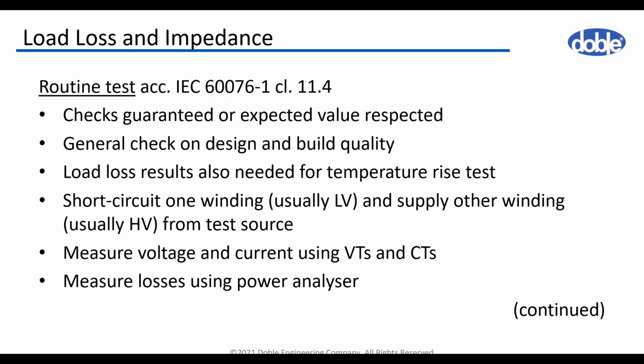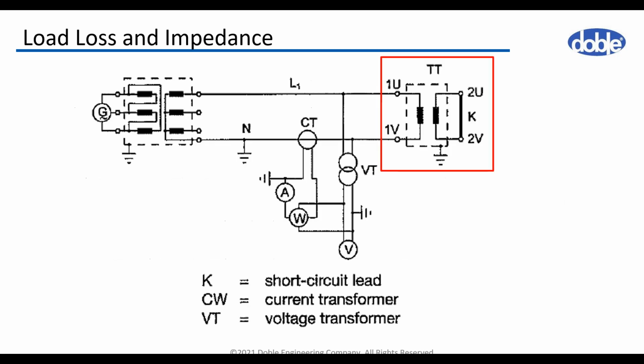How is the test performed? Usually by short-circuiting one of the windings. It's more convenient to do this on the LV side and supply the other winding from the test source. The supply is usually on the high voltage side. So I will move to the next slide, where you can see the test circuit diagram.